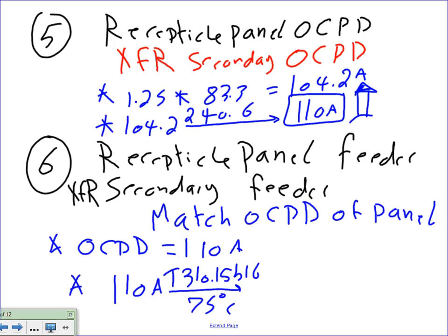And now, how many conductors and why? And what size? How many conductors? I need at least three phase conductors, right? And then I need a neutral because I have a neutral on the secondary side. Should I pull a full neutral? Absolutely. Anything 200 amps or less, full neutral. So this is a 4-conductor. Everybody knows why 4 conductors? Full neutral, 200 amp or less.